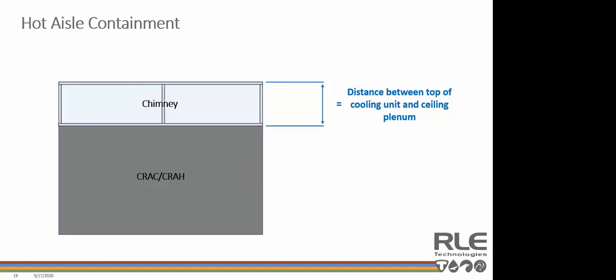So here's an example about using chimneys with a CRAC unit. As mentioned, with hot aisle containment, CRAC units are typically fitted with a chimney to span the gap from the top of the cooling unit to the ceiling return air plenum. These are often made out of sheet metal, but they can also be made out of the same materials as rigid containment.